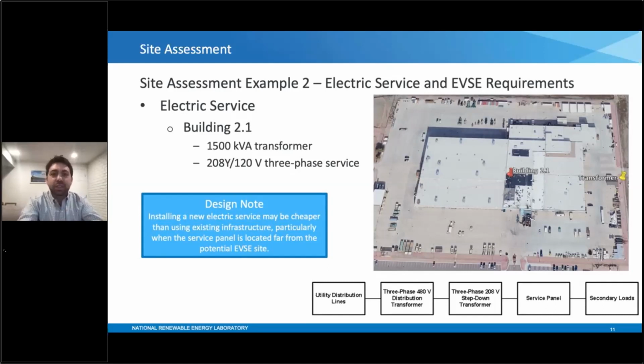The other challenge here, though, is as you can see, the transformer on the right is outside of this parking area, where the building is on the interior of the parking structure. So all the service panels will be inside of that building. So it's important to consider, if you're installing a new electric service, that may be a better option than, for instance, trenching underground. As you can see, most of these vehicles are parked on the outside perimeter of the parking structure. So to supply some EVSE to these locations, we may have to do some trenching, and it's something important to consider. However, installing a new electric service may be cheaper than using existing infrastructure, particularly when the service panel is located far from the potential EVSE site. So in this case, there's the potential that looking at a new service from this distribution transformer may actually be a better approach for this facility.